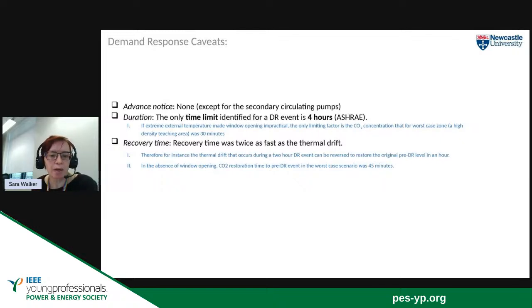We looked only at a maximum of a 4-hour demand response event. This was in line with guidelines from ASHRAE, which is the American association that sets various guidelines for building services engineers. So that was the maximum that we looked at. And as I said before, recovery time was about twice as fast as the thermal drift time. So that gives us an opportunity also to think, how quickly could we offer a subsequent demand response event? If we were asked to offer demand response and we did it for 4 hours, we'd need 2 hours before we could offer it again, because we'd need to wait for the building to get back up to comfort conditions before offering another demand response event.